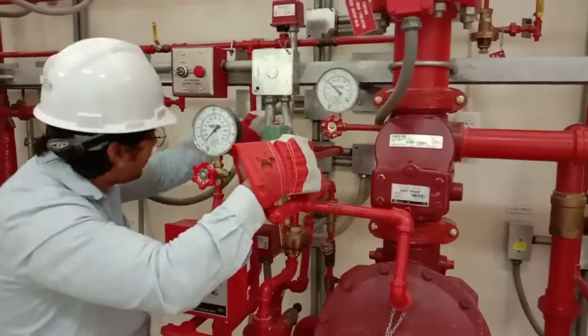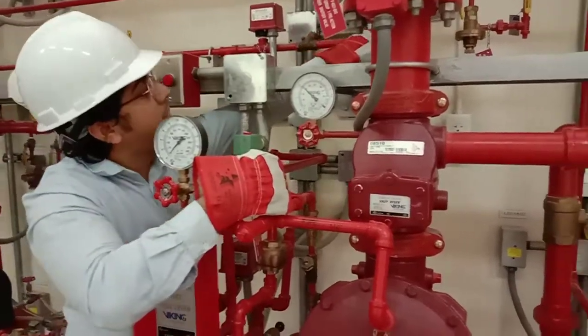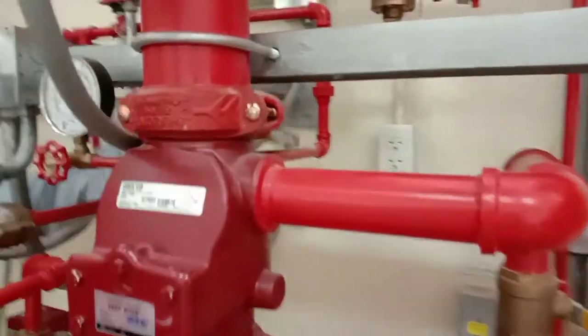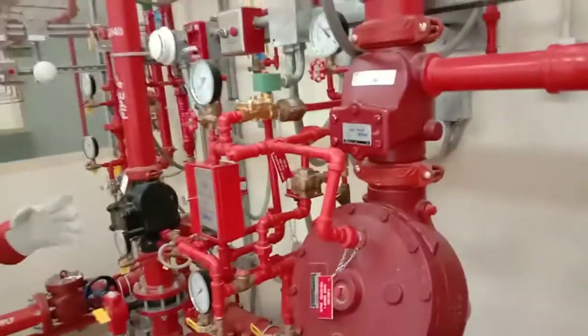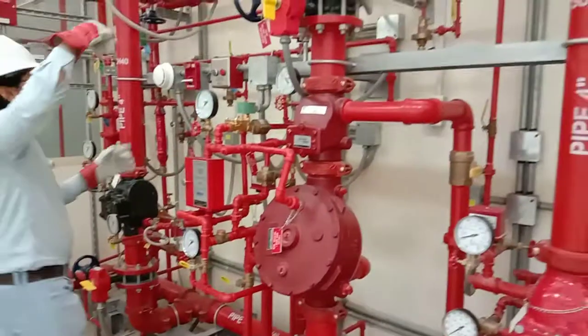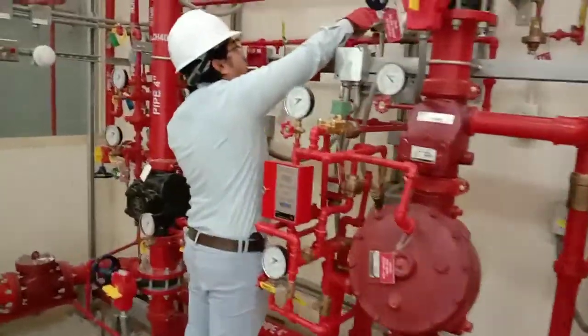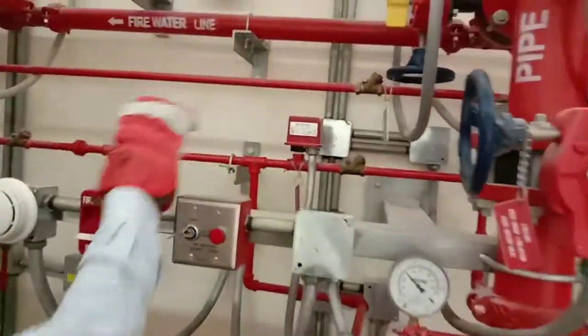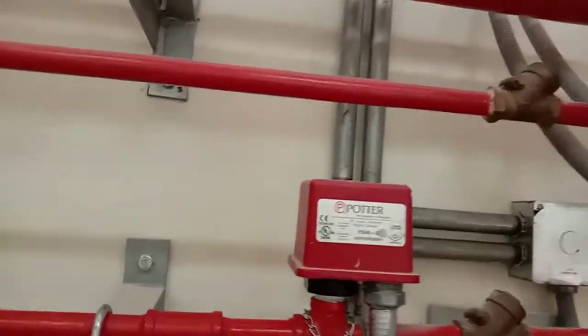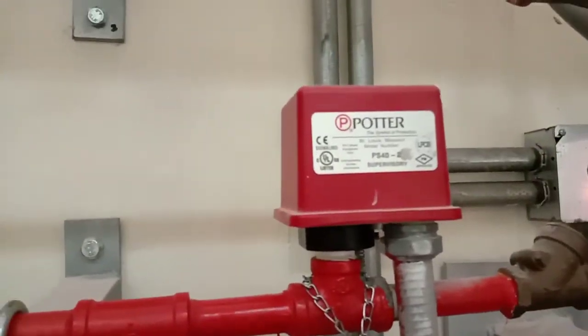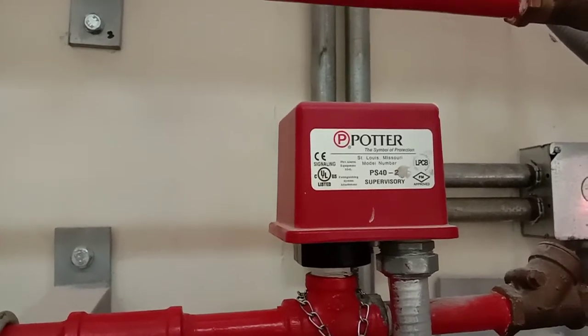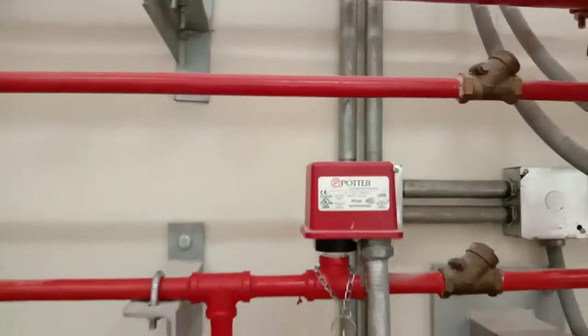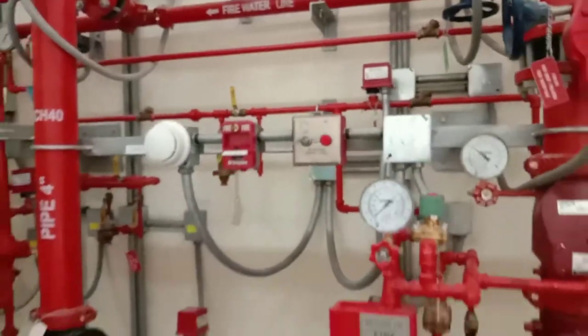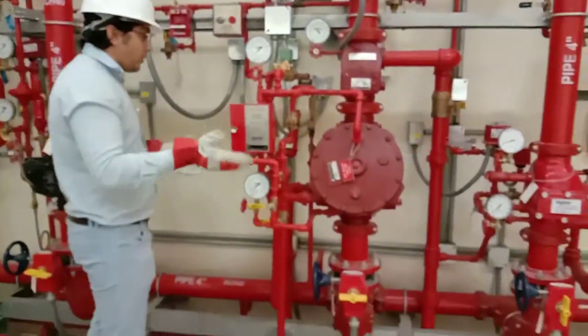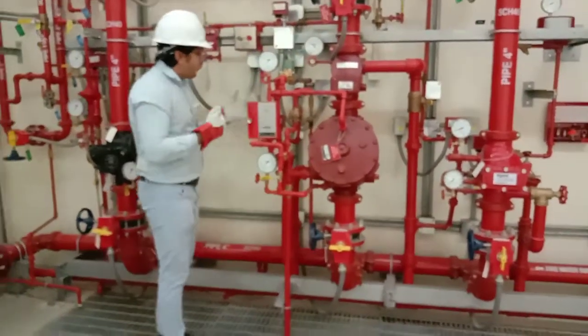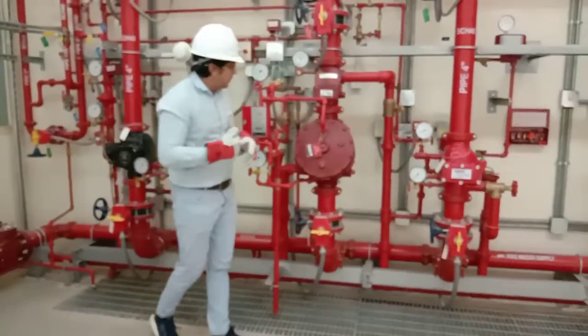Here we have the air line coming all the way from the back of the check valve, so it will close from the top side. Now if you can see the supervised valve at the bottom, if you can focus on that, the function of that is to give the low pressure alarm and high pressure alarm for the air system, right? So if the pressure is much higher, it will delay the activation of the pre-action valve, and if the pressure is low, it will try to open this valve even without fire. So we have to be careful regarding those things.